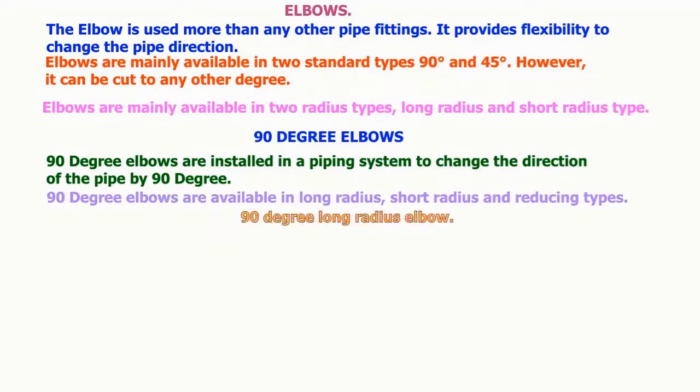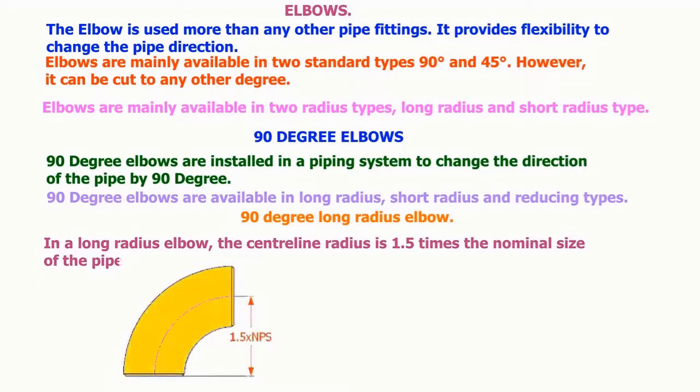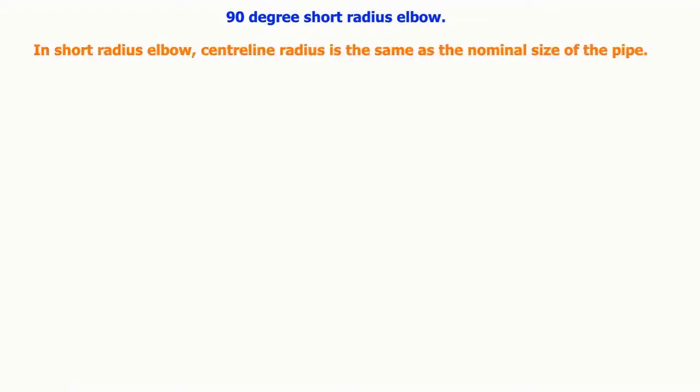In a long radius elbow, the centerline radius is 1.5 times the nominal size of the pipe. In short radius elbow, centerline radius is the same as the nominal size of the pipe.